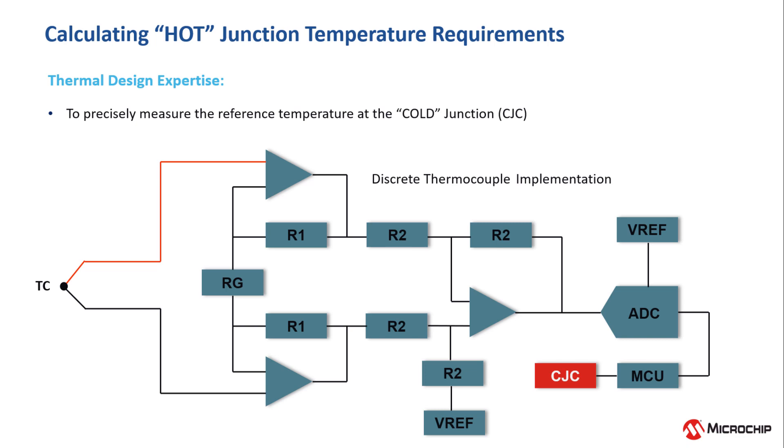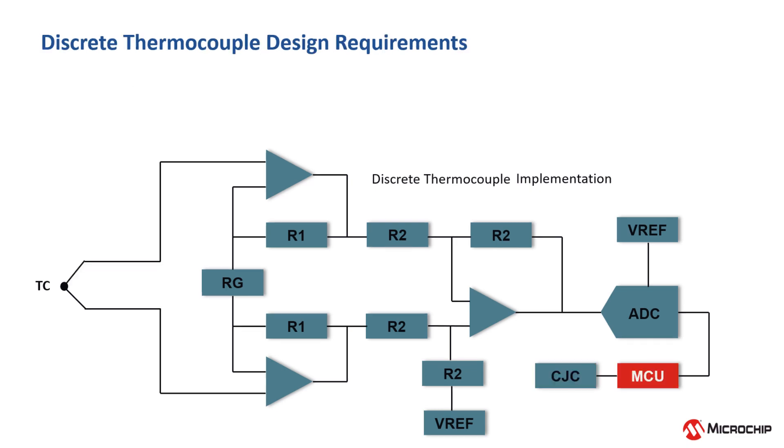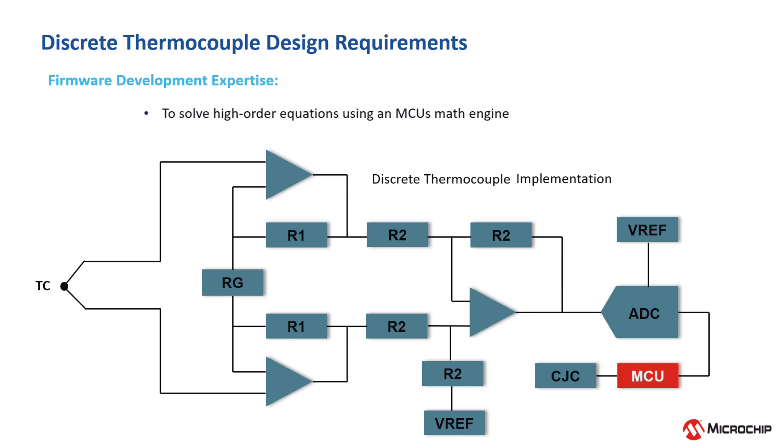Depending on the application, this can be accomplished by using thermistors, RTDs, or silicon-based temperature sensing devices. Lastly, each thermocouple type has a higher order equation that must be computed using the cold junction temperature and the voltage measured at the cold junction.